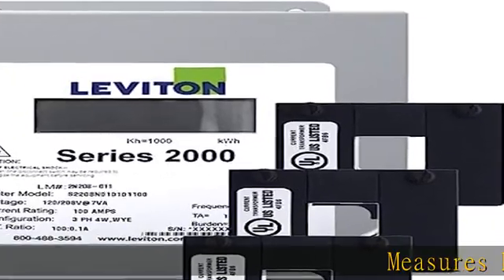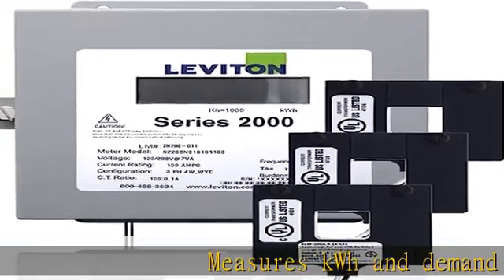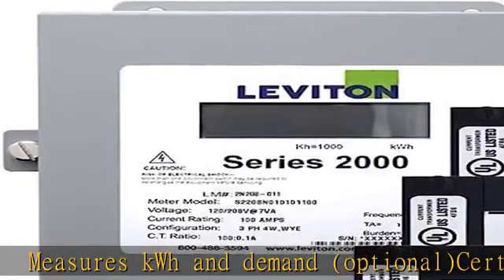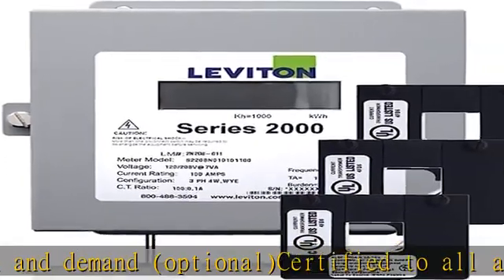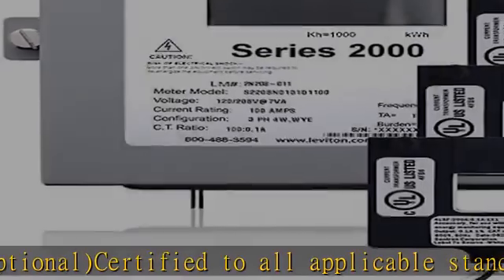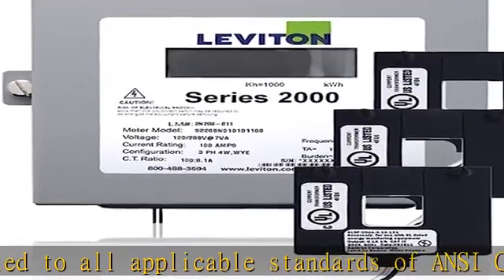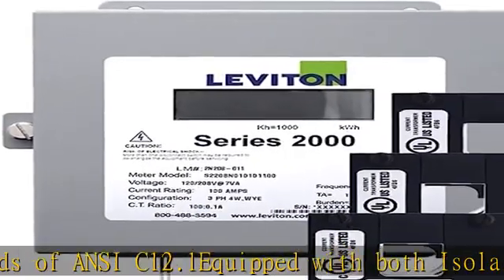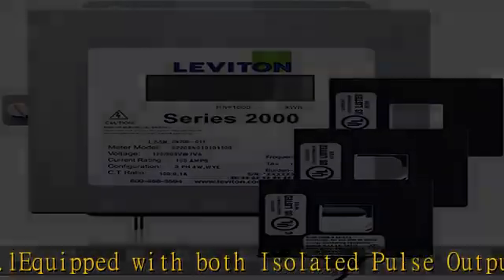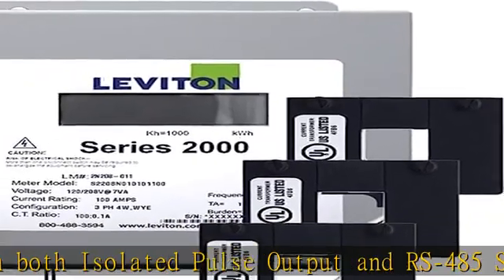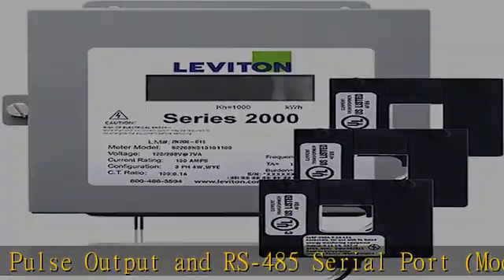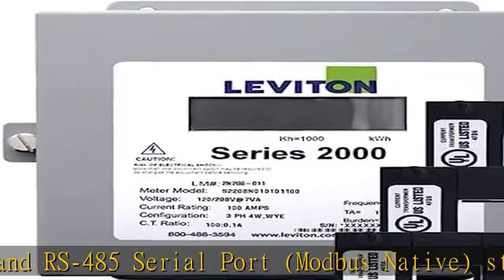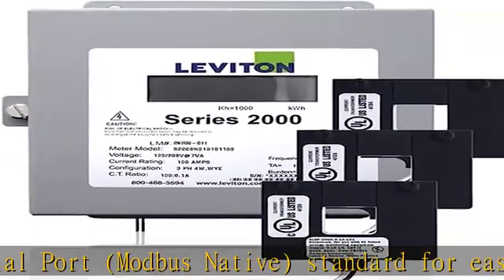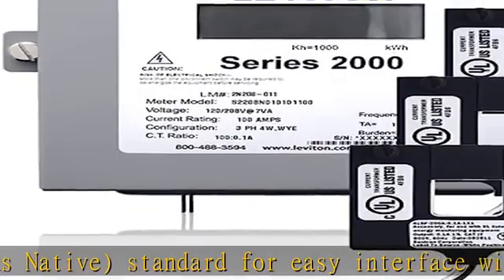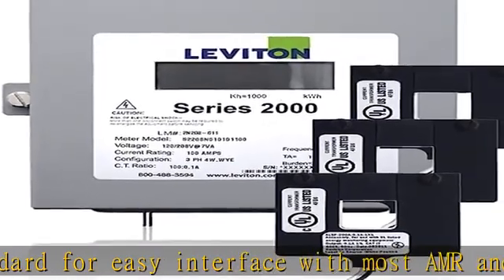Measures kilowatt hour and demand (optional), certified to all applicable standards of ANSI C12.1, equipped with both isolated pulse output and RS485 serial port, Modbus native, standard for easy interface with most AMR and BAS systems. Utilizes revenue grade 0.3 accuracy class, 0.1A secondary solid core current transformers (CTs) that conform to all applicable ANSI requirements, or 1% accuracy split core CTs. Up to 3 sets of CTs per phase can be paralleled per meter.